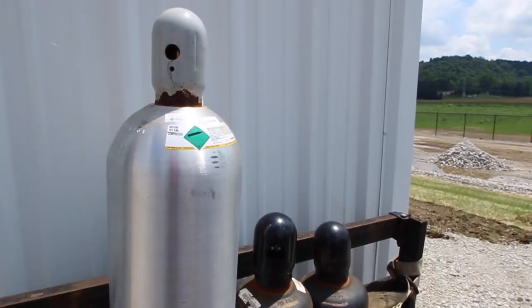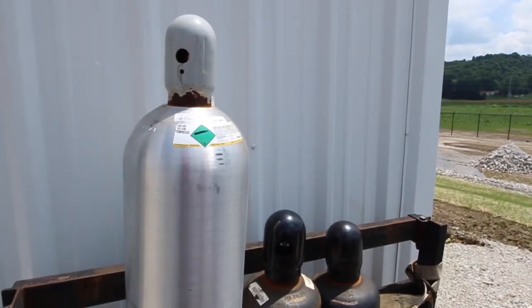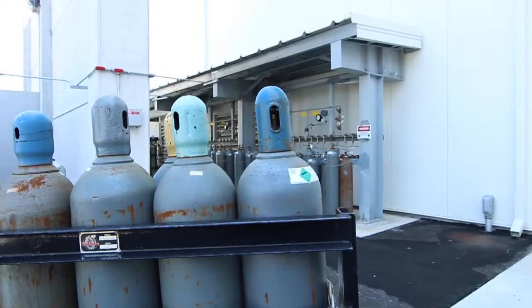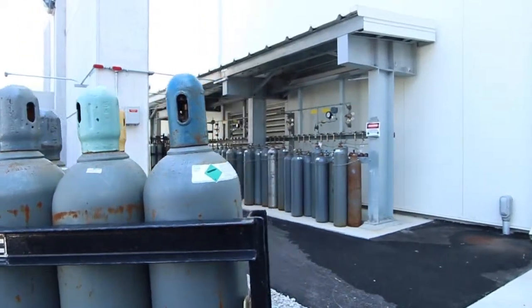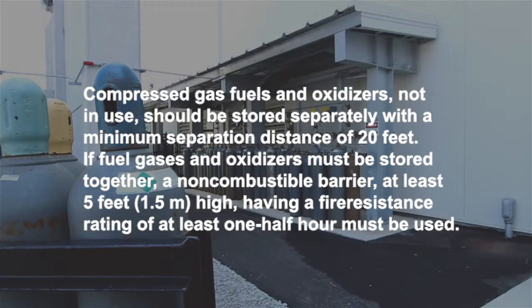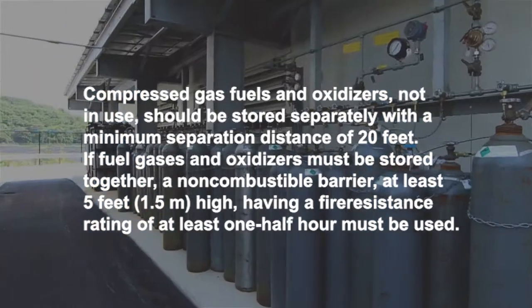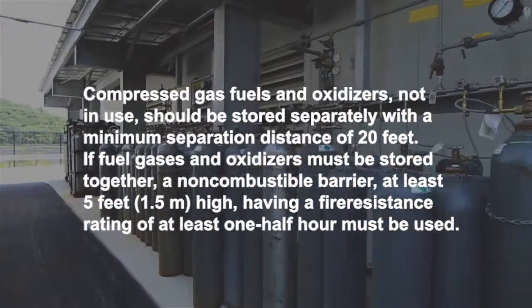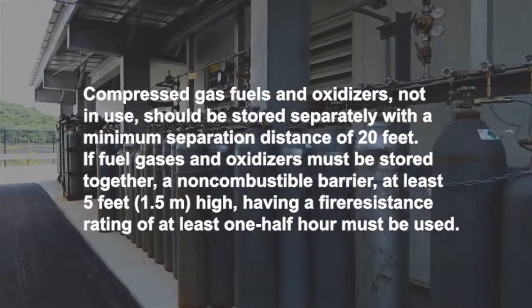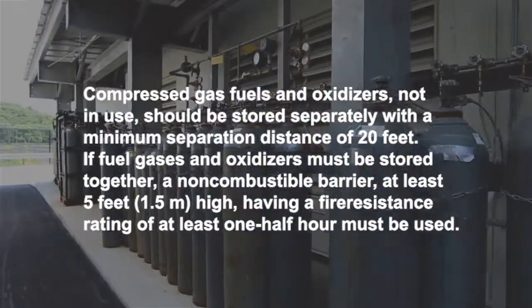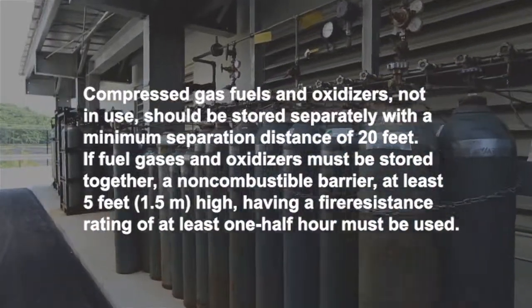Compressed gas cylinders. All compressed gas cylinders must be stored in an upright, secured position with regulators removed and protective valve caps in place. Compressed gas fuels and oxidizers not in use should be stored separately with a minimum separation distance of 20 feet. If fuel gases and oxidizers must be stored together, a non-combustible barrier of at least 5 feet or 1.5 meters high, having a fire resistance rating of at least 1/2 hour, must be used.